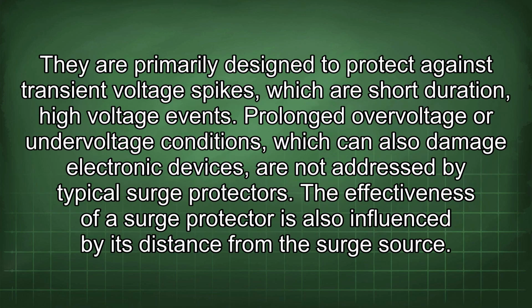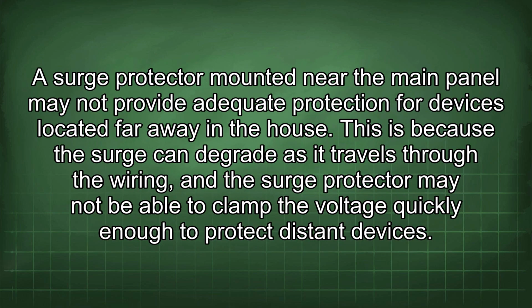They are primarily designed to protect against transient voltage spikes, which are short-duration, high-voltage events. Prolonged overvoltage or undervoltage conditions, which can also damage electronic devices, are not addressed by typical surge protectors. The effectiveness of a surge protector is also influenced by its distance from the surge source. A surge protector mounted near the main panel may not provide adequate protection for devices located far away in the house. This is because the surge can degrade as it travels through the wiring, and the surge protector may not be able to clamp the voltage quickly enough to protect distant devices.